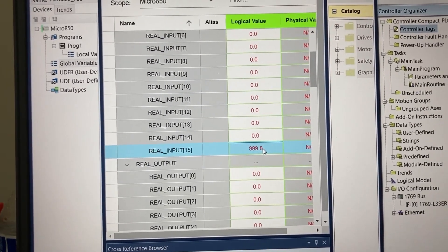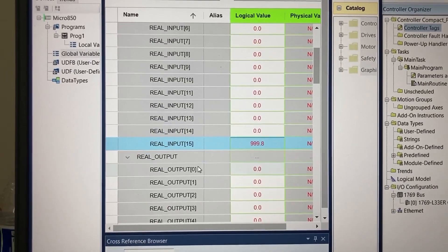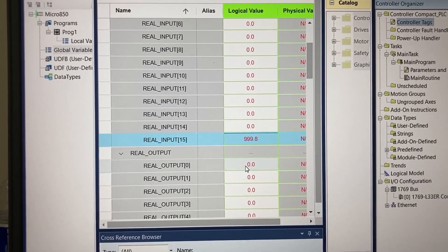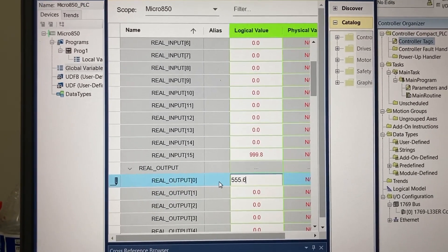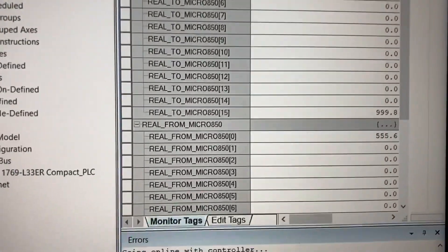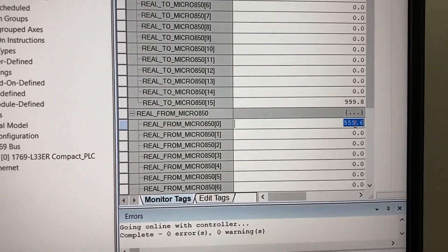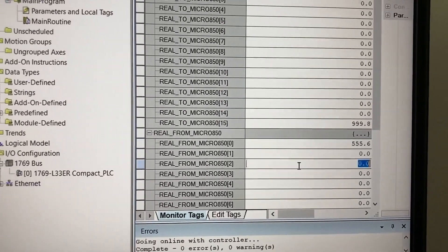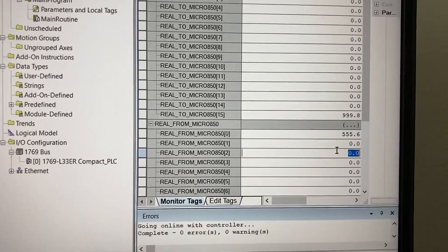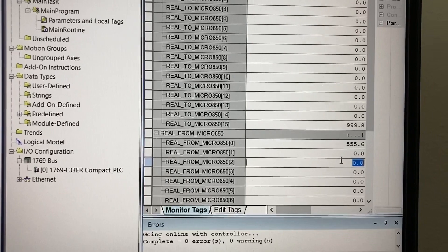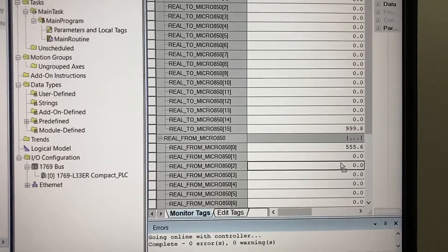Now let's try Real Output from Micro 850 to CompactLogix PLC. First, element 0: 555.6. And on the CompactLogix side, Real From Micro 850 element 0 also shows 555.6. Because it is the input from the Micro 850, we won't be able to enter anything from the CompactLogix — it will reject it.